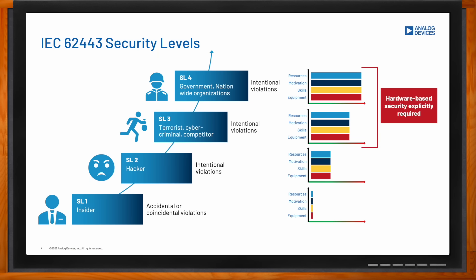IEC 62443 considers four security levels. At the bottom, Level 1 is related to accidental or non-intentional violations where the resources and motivation of hackers are low. At the top, Level 4 corresponds to intentional violations by government or nationwide organizations with virtually unlimited resources and highly skilled personnel. Levels 2 and 3 fall in between, related to intentional violations with varying levels of resources, motivation, and skills.